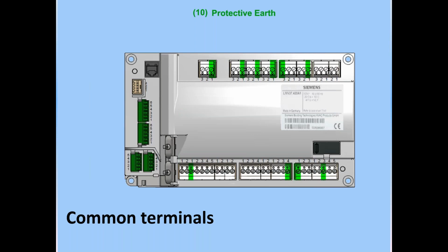It's very common in Europe to use the LMV3 itself as the terminal strip. In the United States, we pretty much have a dedicated terminal strip where we often daisy chain multiple terminals. But the LMV3 provides these, so you could use the LMV3 as a direct termination. We also have several neutral terminals, the incoming neutral on the bottom, and then additional neutral terminals, such as connecting up for the fuel valves and the ignition and pilot.